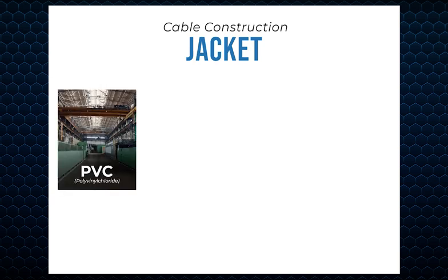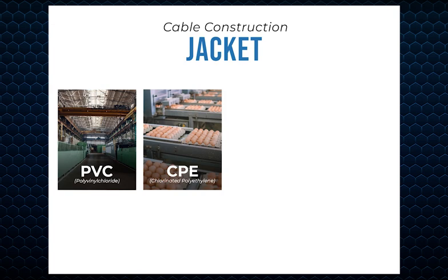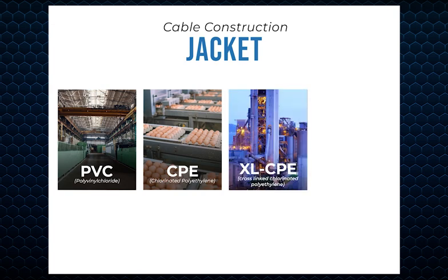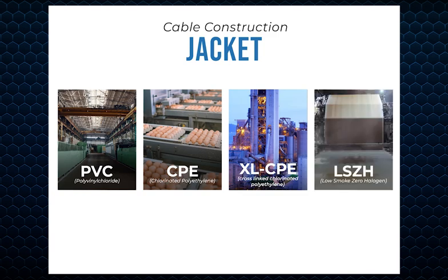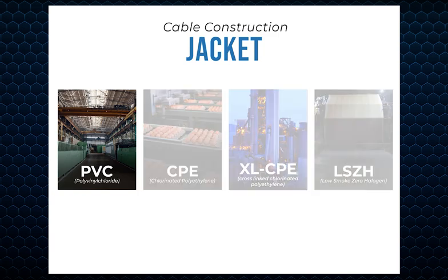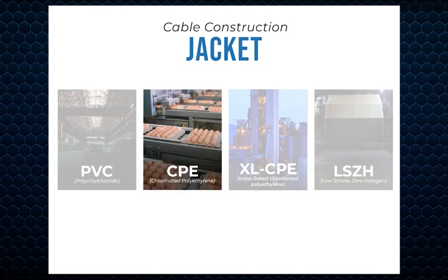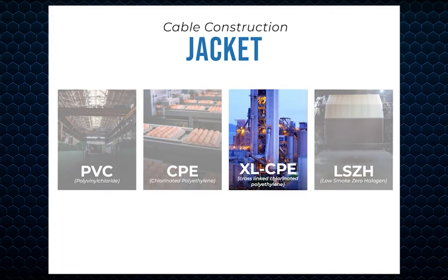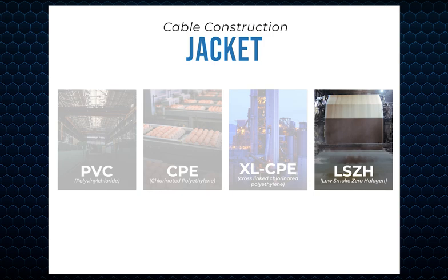There are 4 common jacket compounds: polyvinyl chloride, PVC, chlorinated polyethylene, CPE, cross-linked chlorinated polyethylene, XLCPE, and low-smoke zero halogen, LSZH. PVC is a low-cost option and is more durable. CPE is a higher performance jacket. It burns to ash when exposed to flame. XLCPE is used for harsh environments. Low smoke zero halogen does not emit harmful gases or smoke when burned.